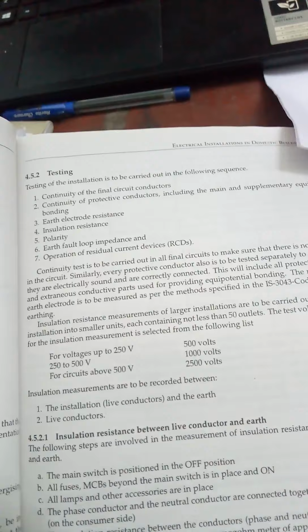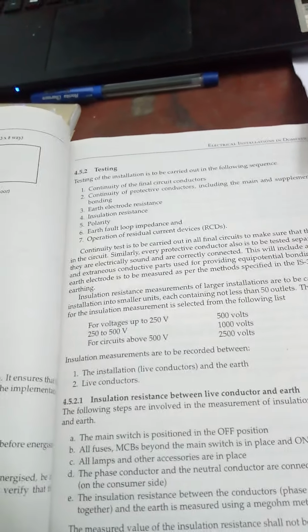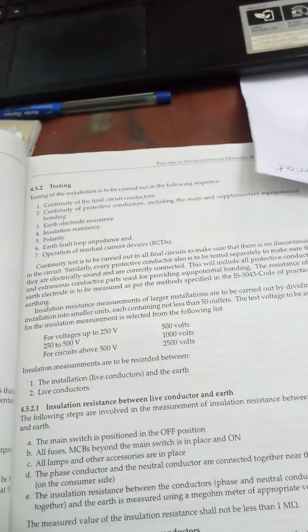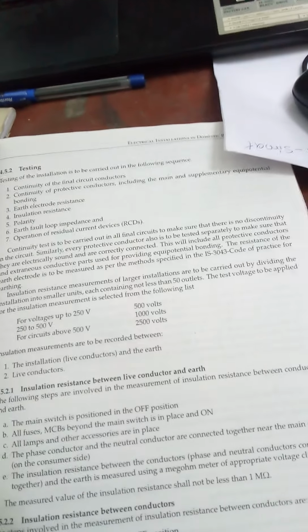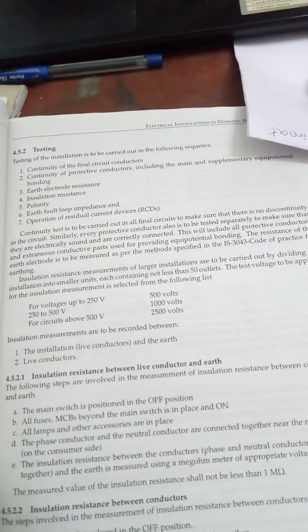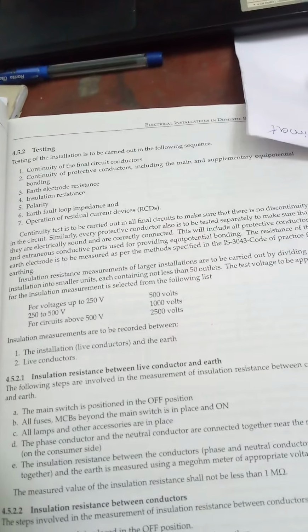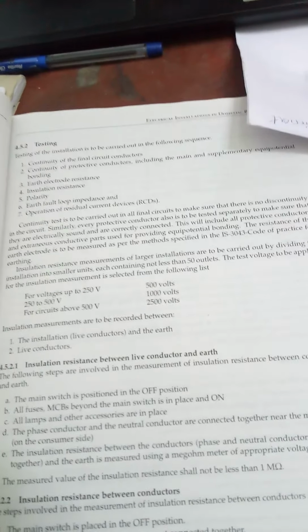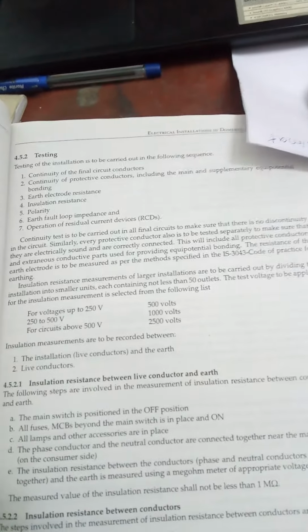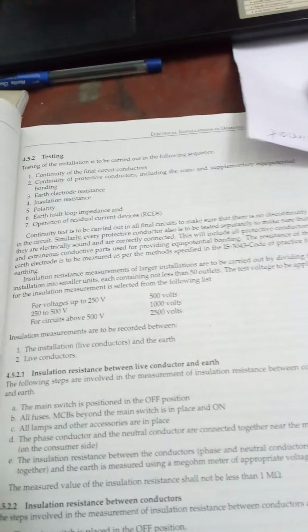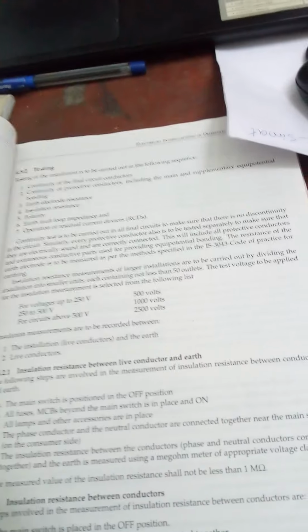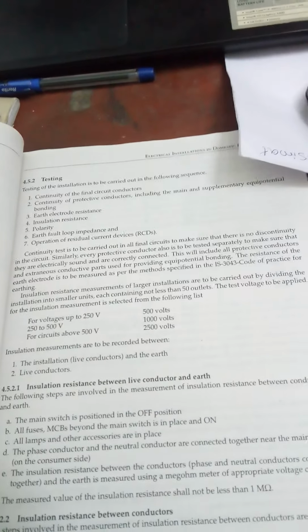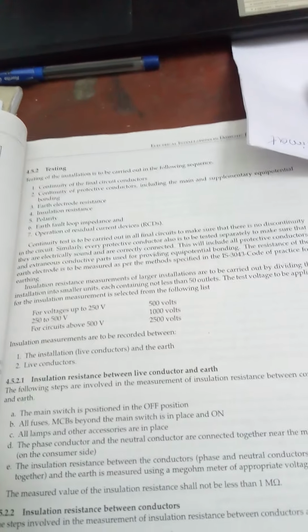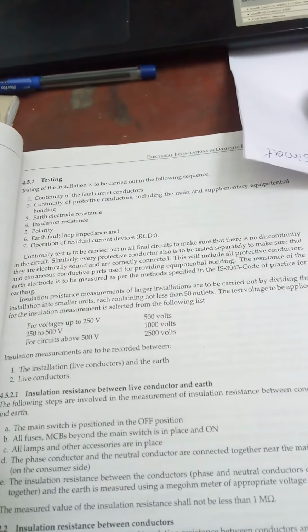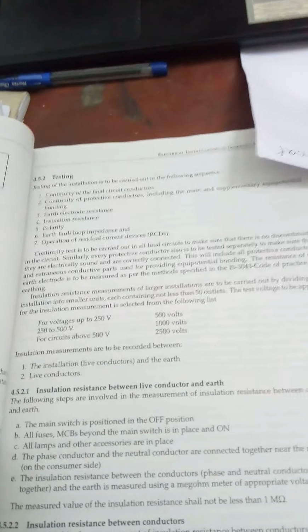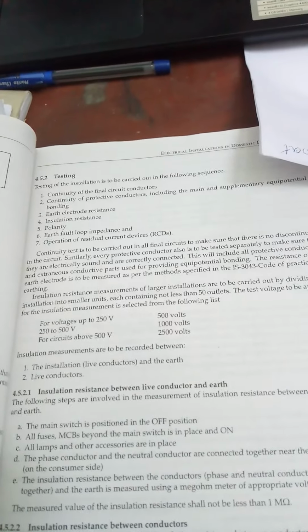Insulation measurements are recorded between the installation and the earth and between the line conductors. The steps followed in the measurement of insulation resistance between conductor and earth are: the main switch is positioned in the off position. All fuses and MCBs beyond the main switch are in on condition. All lamps and other accessories are in place. The phase conductor and the neutral conductor are connected together near the main switch on the consumer side. The insulation resistance between the phase and neutral conductors connected together and the earth is measured using a megohm meter of appropriate voltage class. The measured value should not be less than 1 megohm.